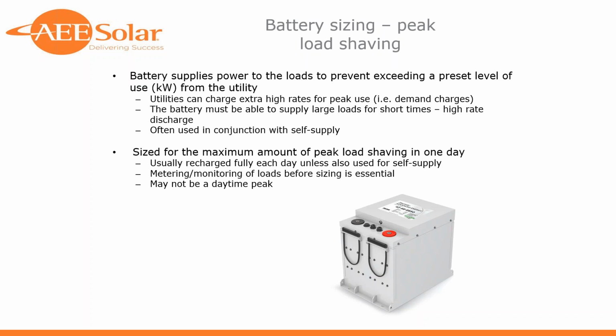Yeah, and in thinking about how we explain this to customers, when we're doing our homework and metering loads, we're trying to find some really peaky loads that, to make this cost effective, can drive a high kW number but maybe don't have a great energy usage through the day. So typically we're thinking about rotating assemblies, motors, pumps, compressors, etc., that when they turn on are going to draw a large amount of current, but maybe not a lot of power through the day. So provided we pick the right battery, we can size it for high current discharge, maybe a couple cycles through a day, but we're not having to put a ton of amp hours towards the solution because it's not a high duty cycle load.